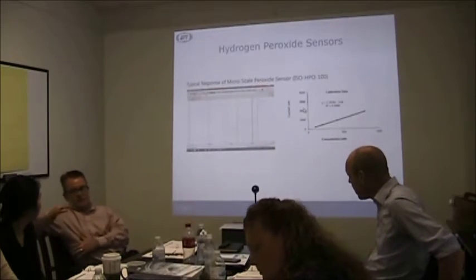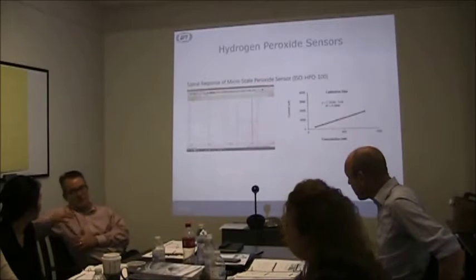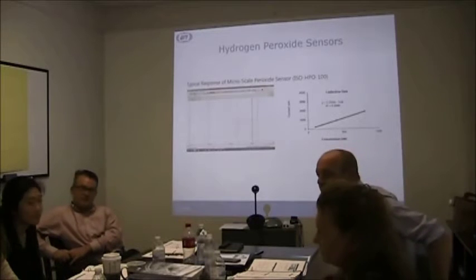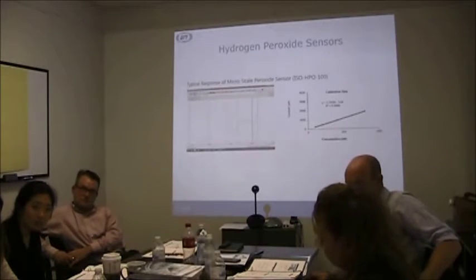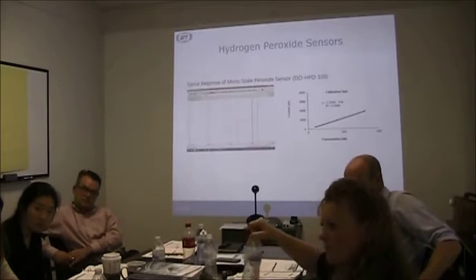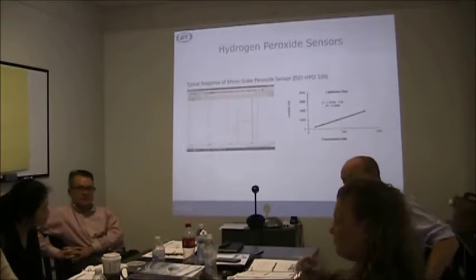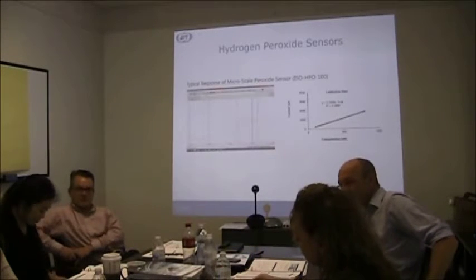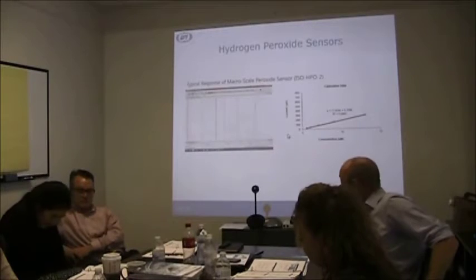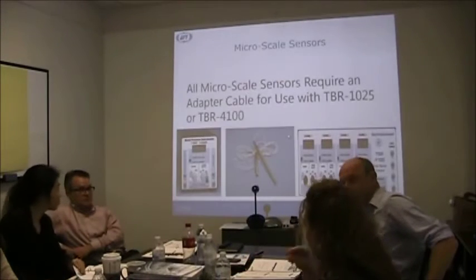What's the relationship between surface area and concentration range? More surface area, more concentration? Generally, bigger is higher. If you double the surface area, as an example, a 4 millimeter length tip as opposed to a 2 millimeter length tip is going to roughly give double the response sensitivity. We don't have a 4, but all the tip lengths of the small sensors can be ordered with custom lengths.